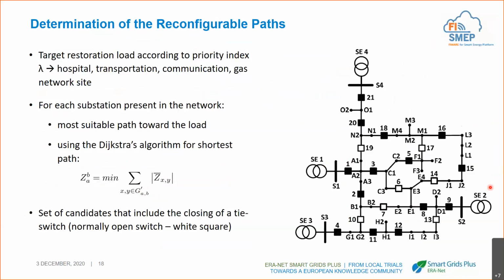Now, a bit more on the situation by considering a larger grid, which is no longer constituted by 2 feeders, but more feeders. We have 4 substations, but the common denominator is that this grid is managed as a radial. So again, we have the normally open switches, which are the white squares, so that the different substations are electrically disconnected. In case we have a fault in one of the points of the grid, again, we have to open the surrounding switches to isolate the fault. And consequently, we have some loads that are now disconnected, de-energized.